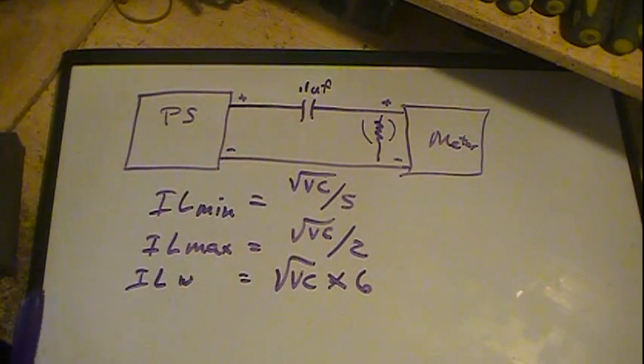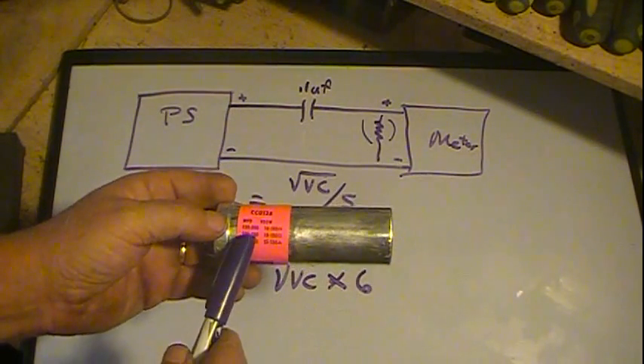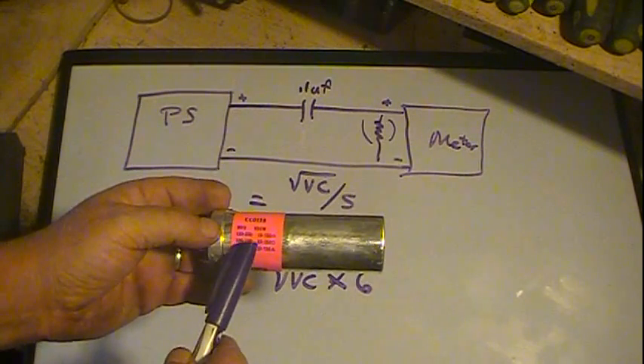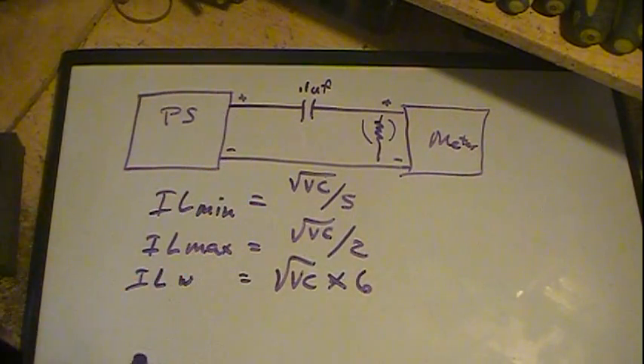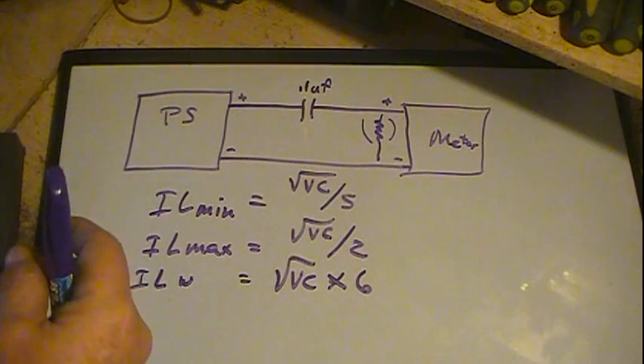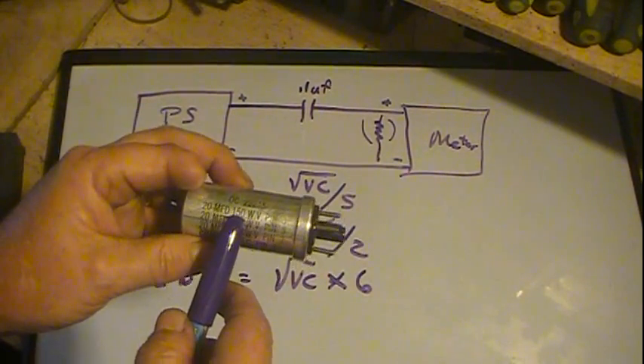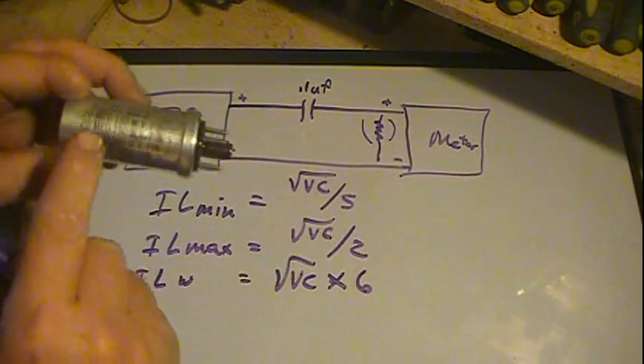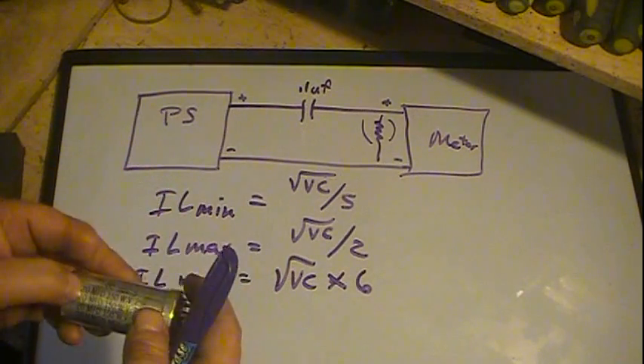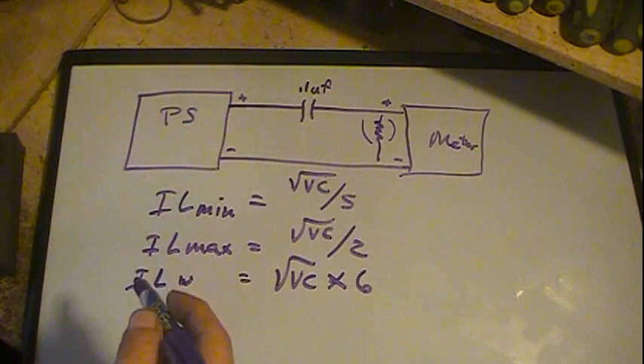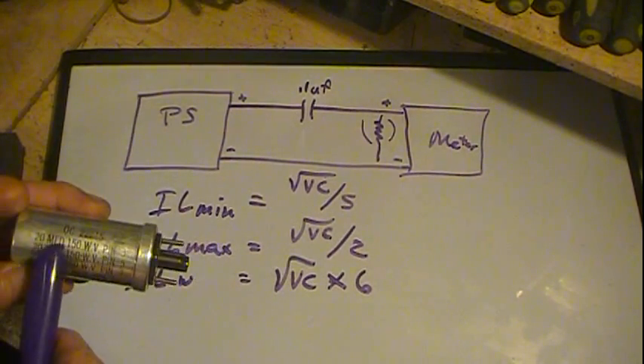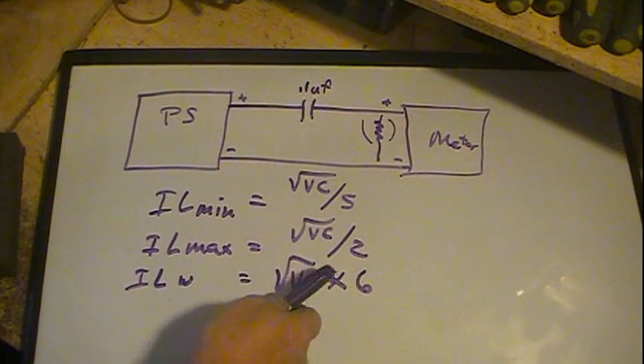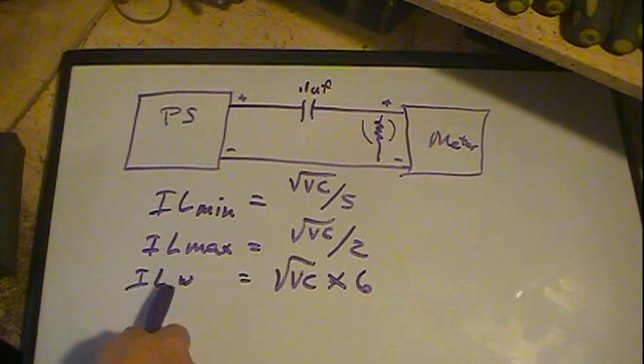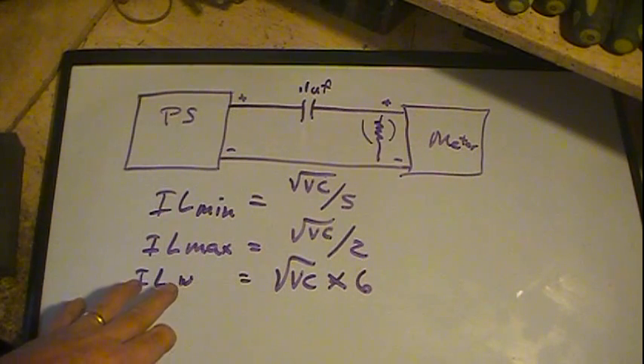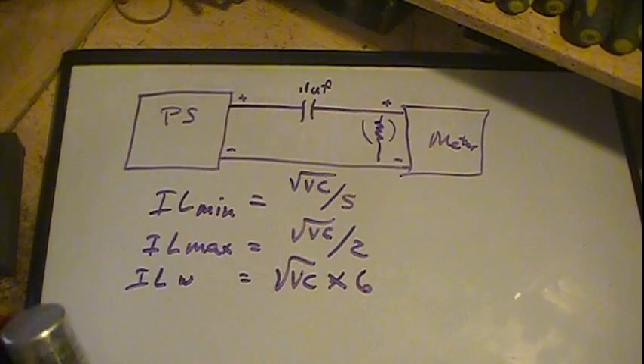V is the rated voltage of the cap. Something like this cap here, rated voltage is 10 to 150 volts. It's not real good when they actually give a range. Let's take this one: 150 working volts. This is 20 microfarads. V is that working voltage. That's the number you'll put in for V. C is the capacitance in microfarads. So since it's already in microfarads, you take 20 times 150, take the square root of that, and take it times 6 to get the worst case scenario leakage current it can be. If it's around that current or above, it's no good.